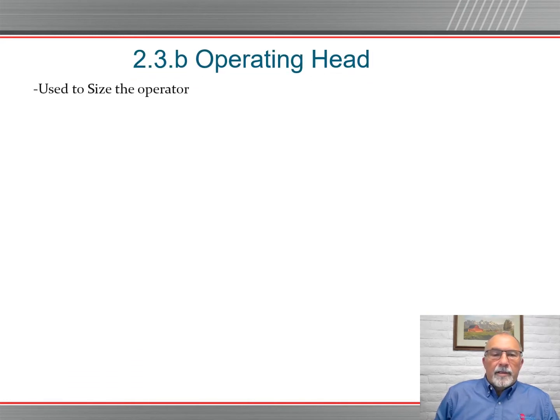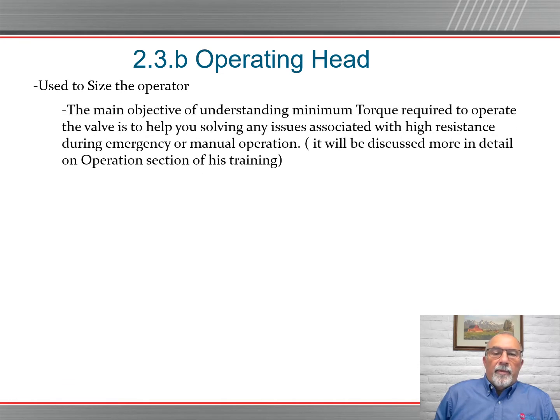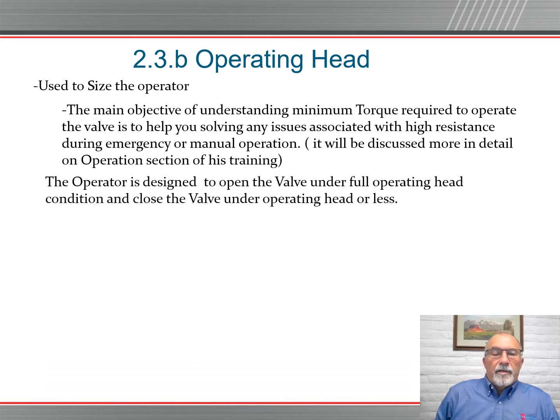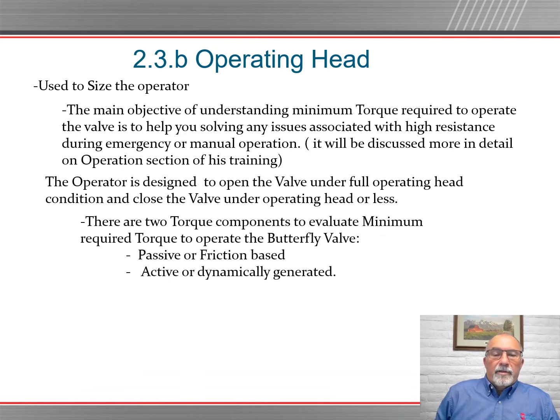The operating head is used to size the operator. The main objective is understanding the minimum torque required to operate the valve to help you solve any issues associated with high resistance that you may have encountered during emergency or manual operation. It will be discussed more in detail in the operational section of this training. The operator is designed to open the valve under full operating head condition and close the valve under operating head or less. There are two torque components to evaluate minimum required torque to operate the butterfly valve: passive or friction based, and active or dynamically generated.